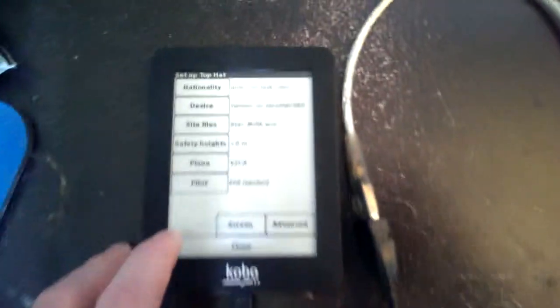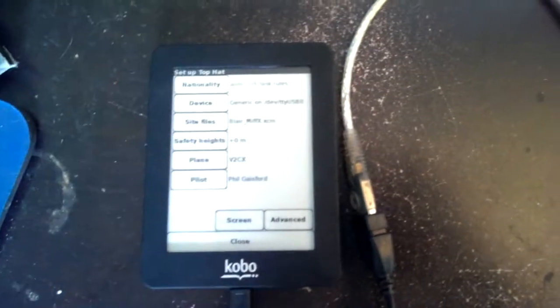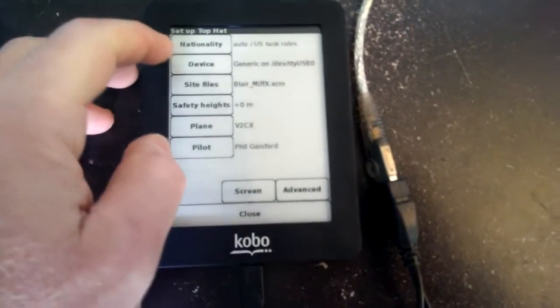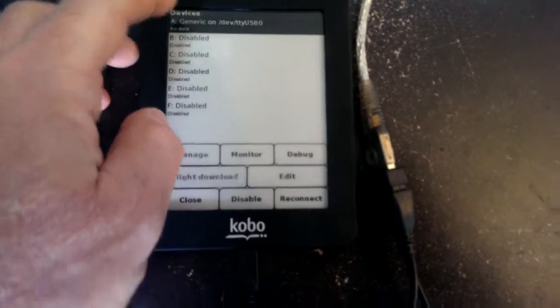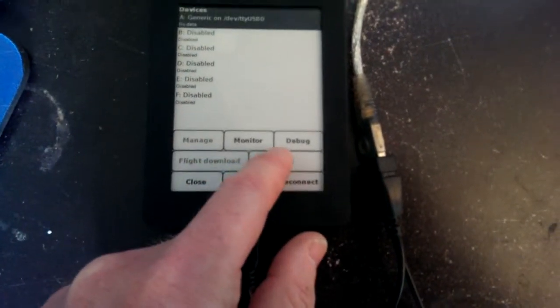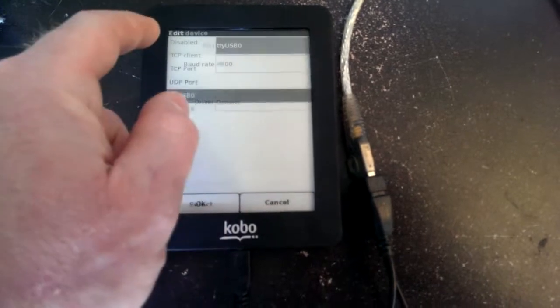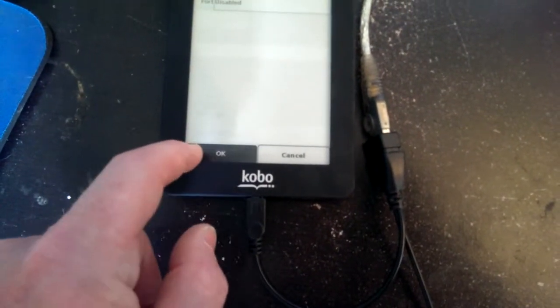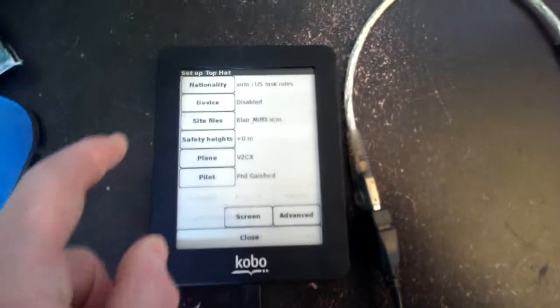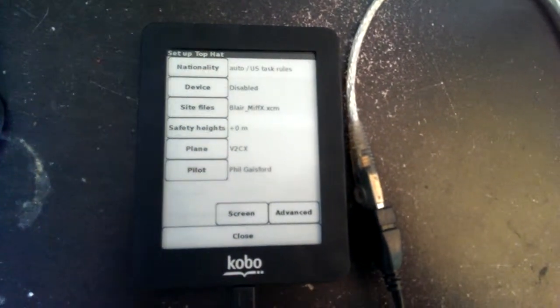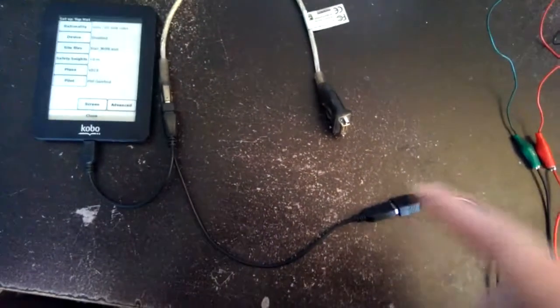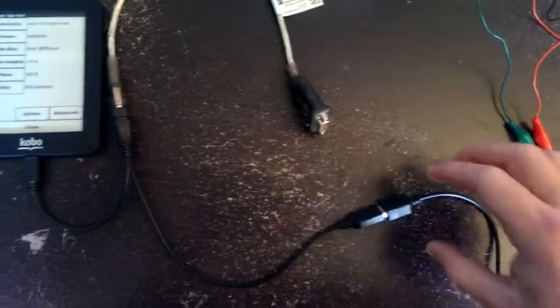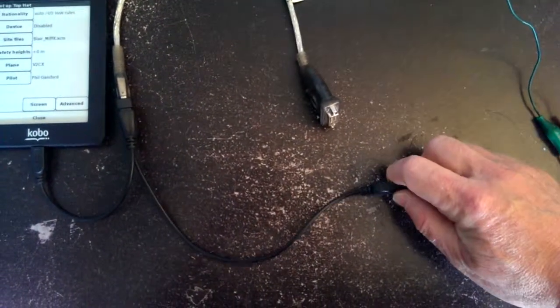So again, I'm going to start at this screen. I'm in fly mode again. I'm going to go into device. And the first thing I'm going to do again is change this to disabled. And then go back to this screen. So now I'm disabled, which means I'm ready to start testing. And let's just disconnect any one of these three points. So let's disconnect the power, for example.